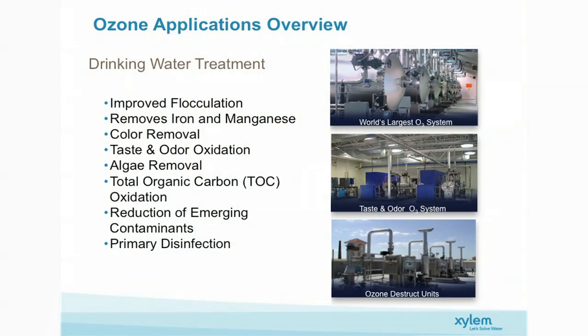Okay, so for the benefit of this audience, I suppose drinking water was the main focus. Why would you use ozone in a drinking water plant? The benefits of using ozone are the improved flocculation that you get with the ozone gas as a result of the bringing down of other elements like iron and manganese. Using ozone precipitates iron and manganese on contact and actually improves the overall flockability of the water. You actually see ozonated treated water has a sparkle to it. You can actually see the clarity of the water. Color removal, very effective at reducing TOC's, color. Taste and odor control. Algae removal, as I said, TOC oxidation.